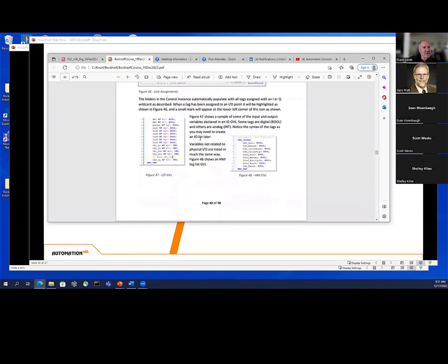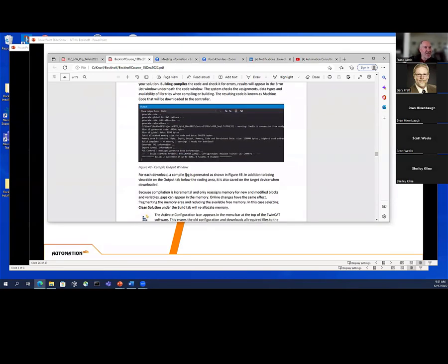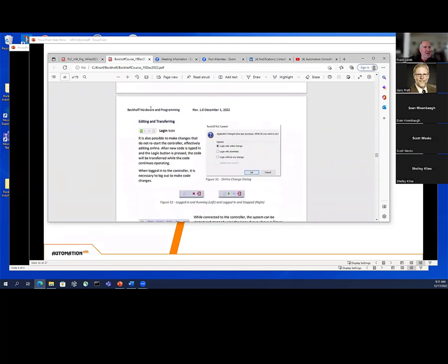I show them how to attach to things, activating configuration — what does that do? Compiling, building the solution, et cetera. I explain what all the little icons mean and some of the pop-up screens. Then editing and transferring — in a lot of ways this is similar to Siemens. When you do your editing and log in with online change, it's not like Allen Bradley where you used to accept edits, test edits, and assemble edits. You just log in with the change and it makes the change. If it's not too severe, it will do it without stopping your processor, so you can kind of online edit with Beckhoff.